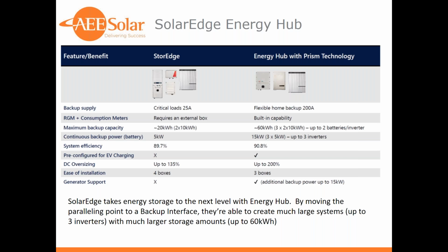So really, to be able to bring more power to bear on a system, they had to move the disconnecting means out of the inverter and somewhere that could control a lot more power with a single contactor. So the big change that fueled all of this was the ability to have a backup interface unit. By moving that disconnecting means and the paralleling means to a standalone piece of distribution equipment, you can strip some of that capability out of the inverter.